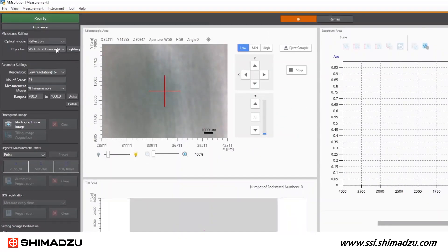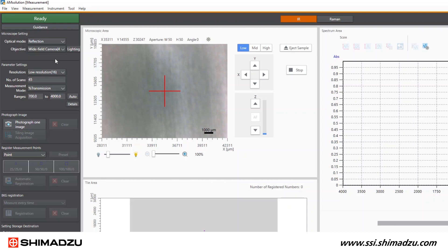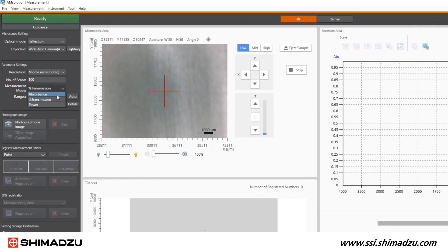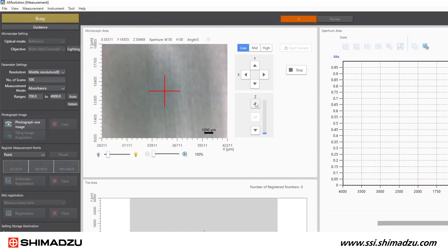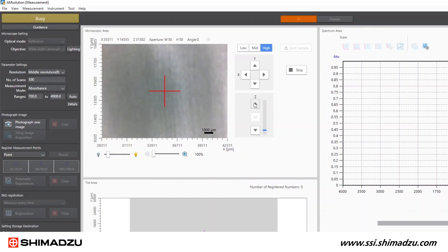Moving one tile down under the parameter settings, we need to select a few more FTIR measurement settings. A resolution of 8 wavenumbers is standard for an FTIR microscope, and that's what I'll use here. 100 scans is a good place to start and will require about two minutes for acquisition. The measurement mode choice is a personal preference because it's simply a math equation to convert between them. I prefer viewing absorbance data, so that's what I'm going to use for this demo. A wave number range of 700 to 4000 wavenumbers is standard for a DTGS detector, and there's no reason to adjust it.